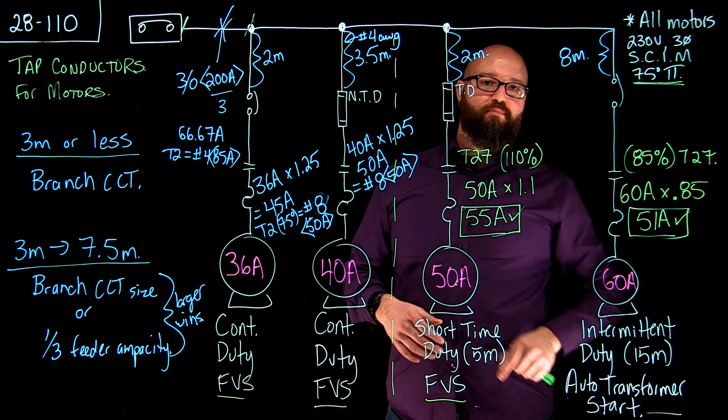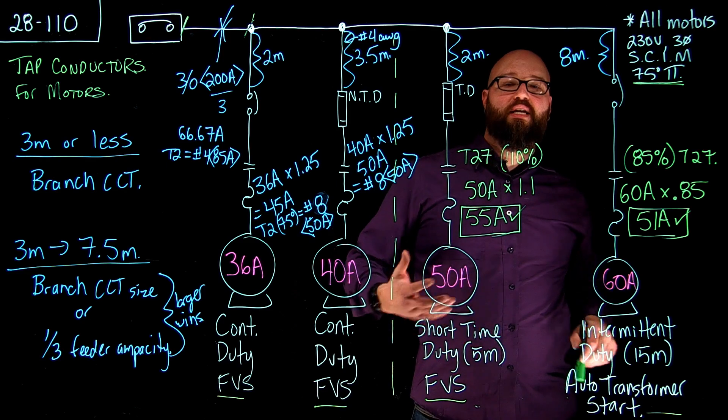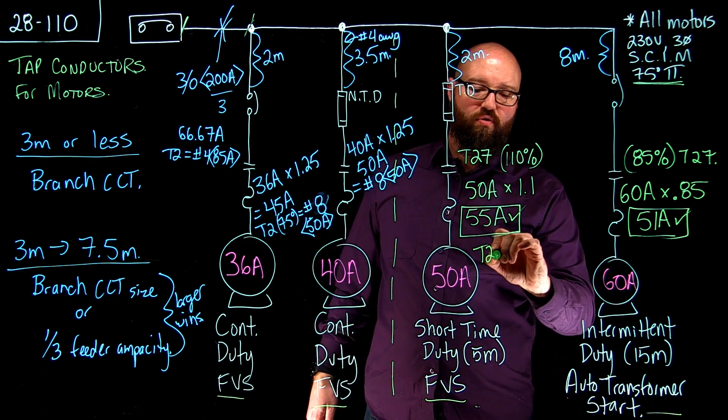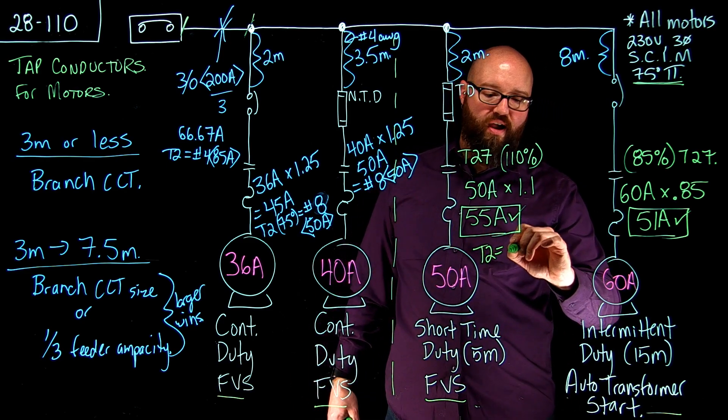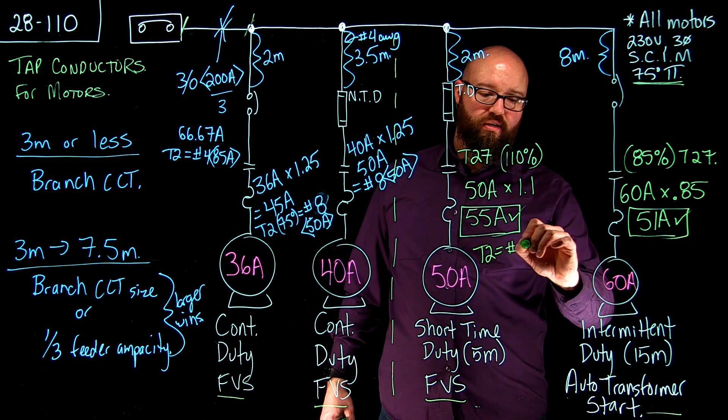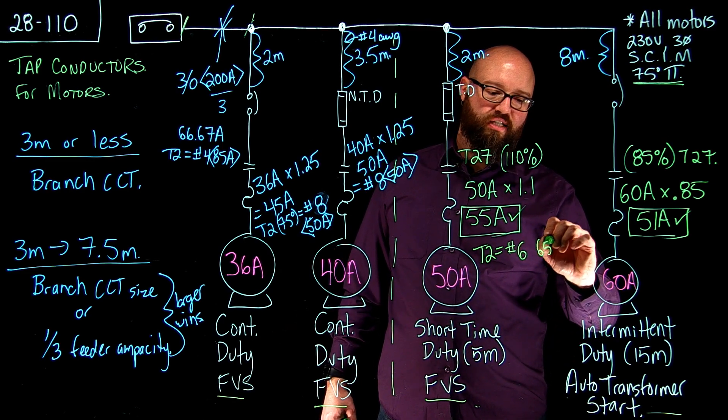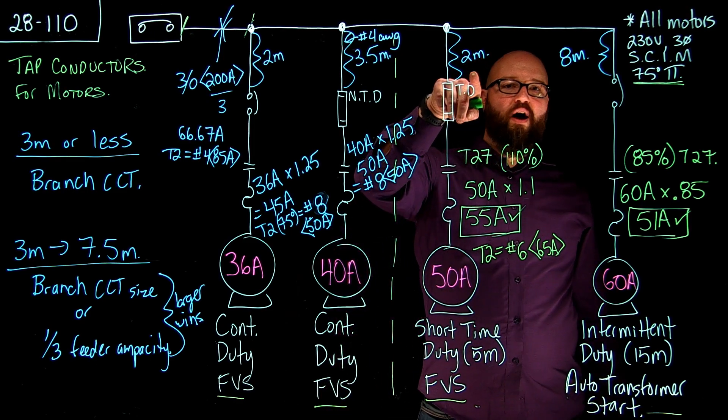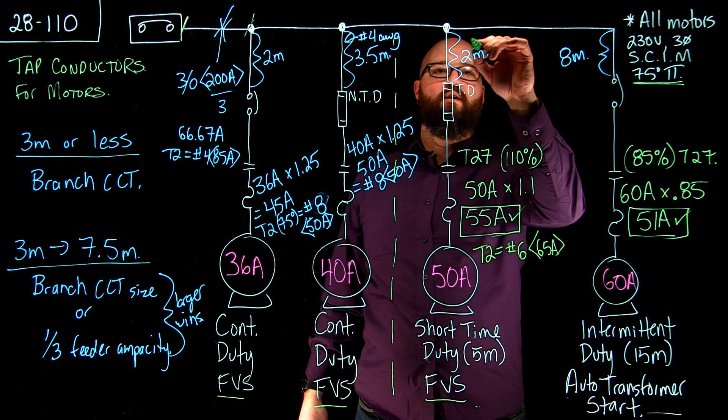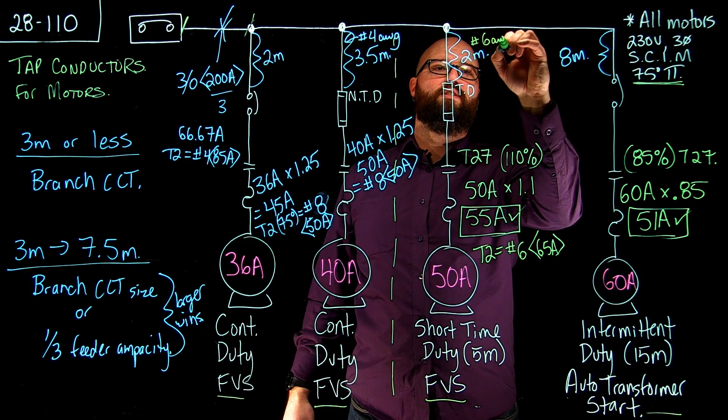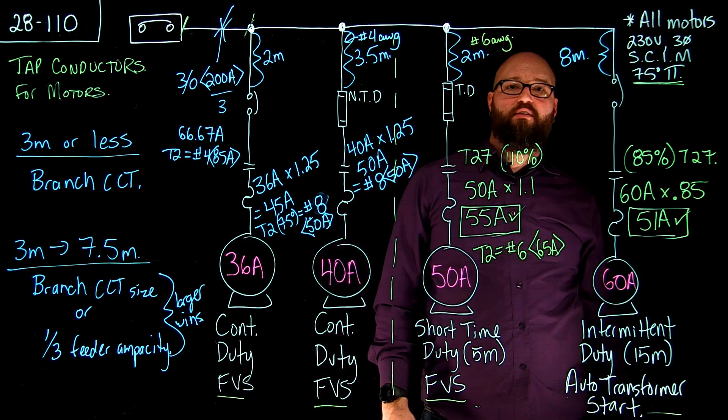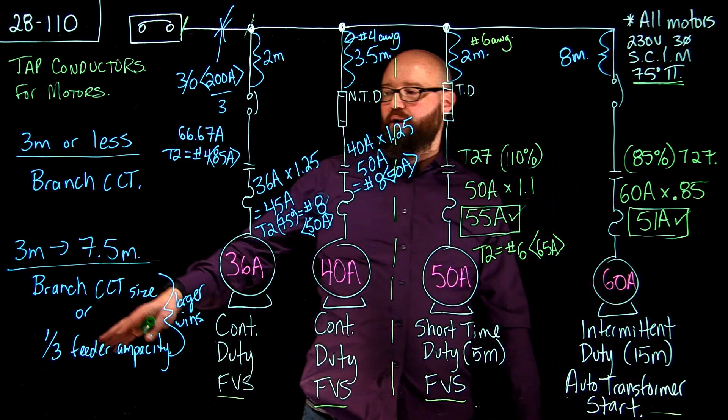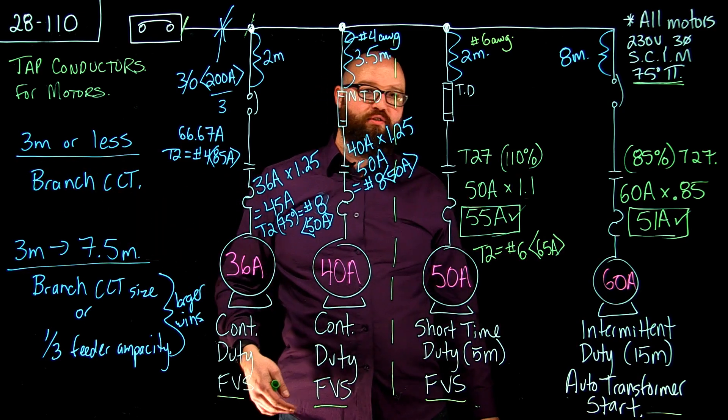Which gave us 55 amps. Now 55 amps I can take that now to table 2 and I can select from there I can go with a number 6 which is good for 65 amps. And again we're under 3 meters so here a number 6 will suffice as a tap conductor. Again I'm not comparing it because we're 3 meters or less.